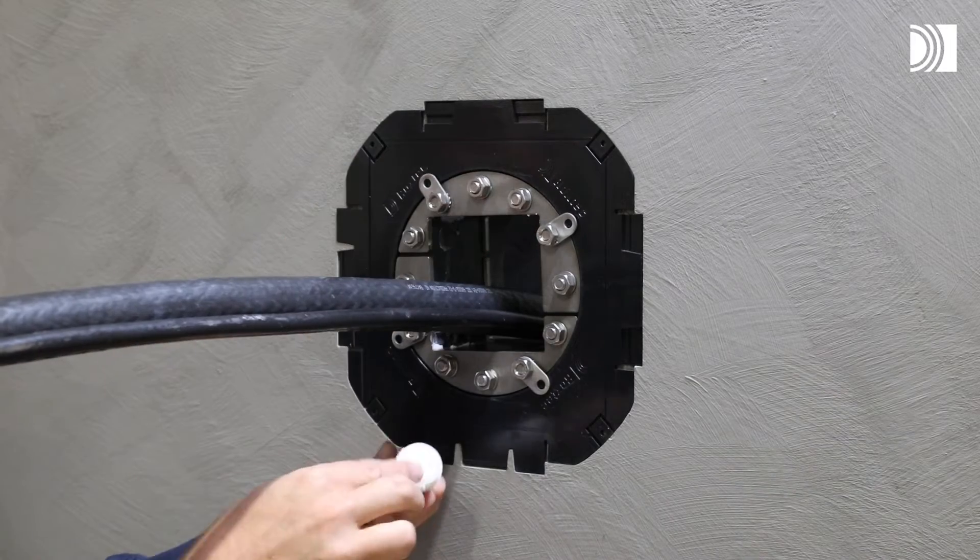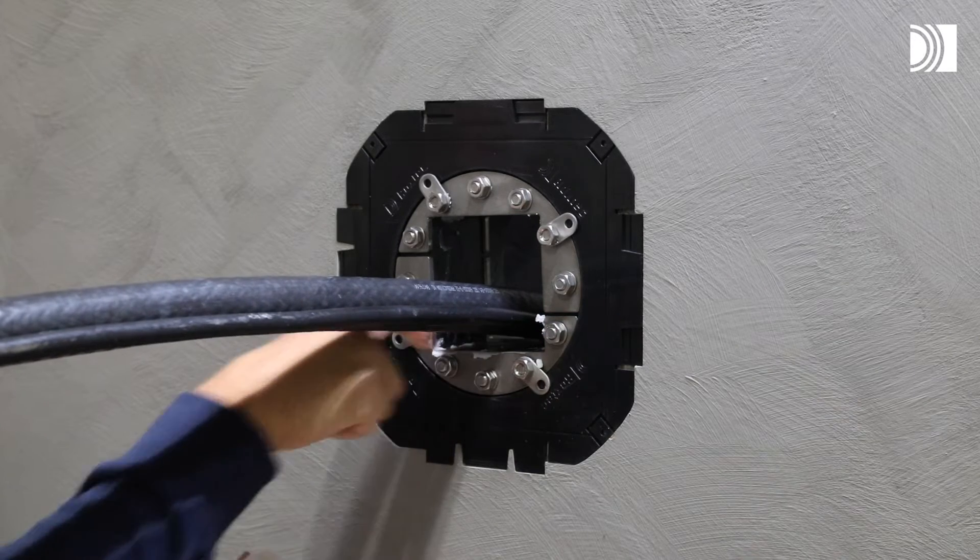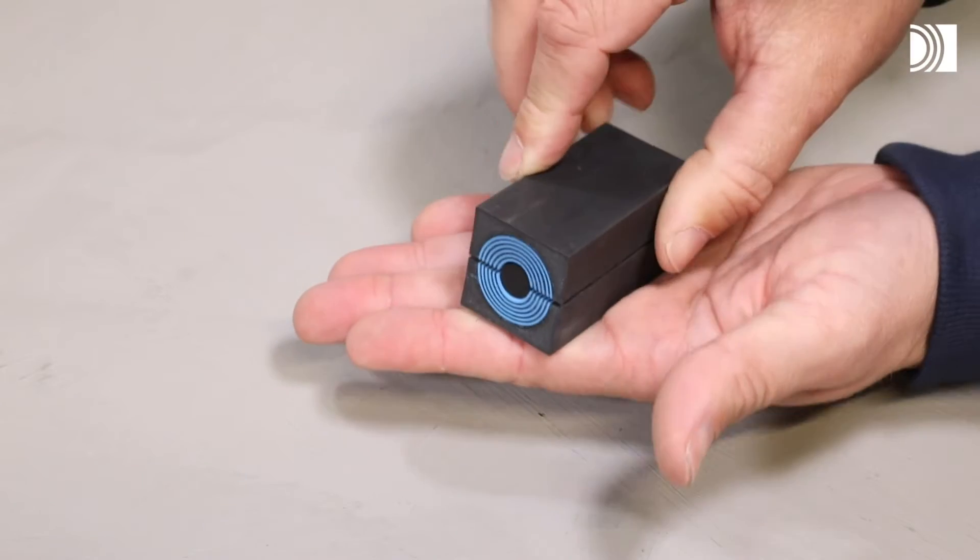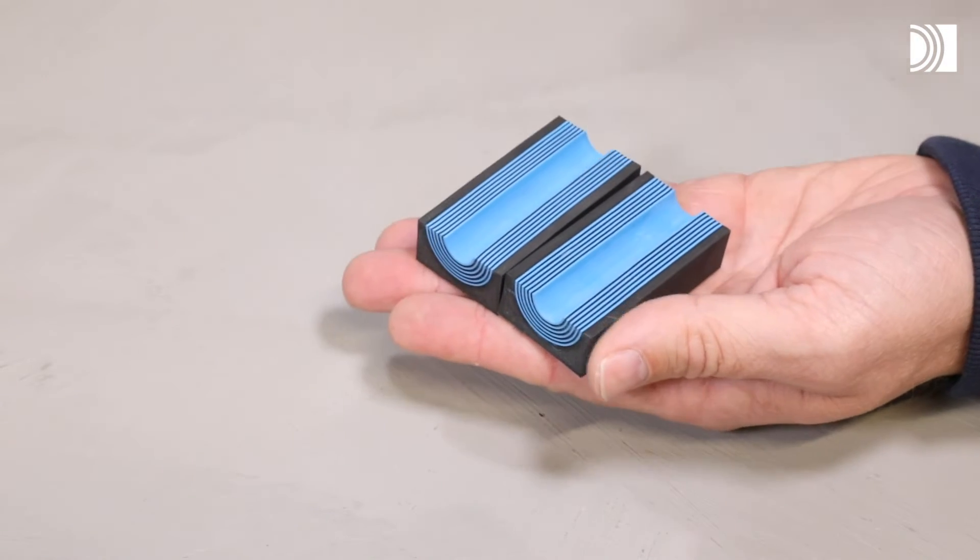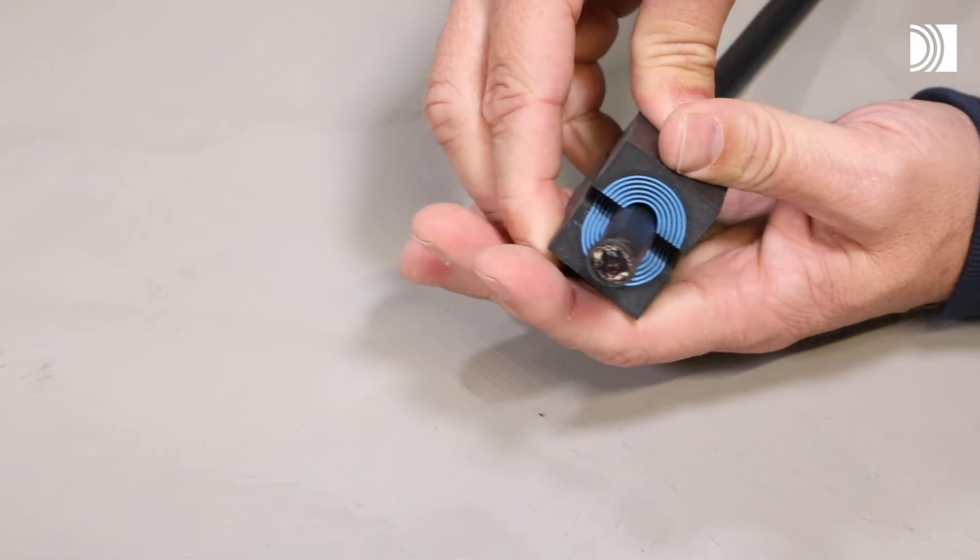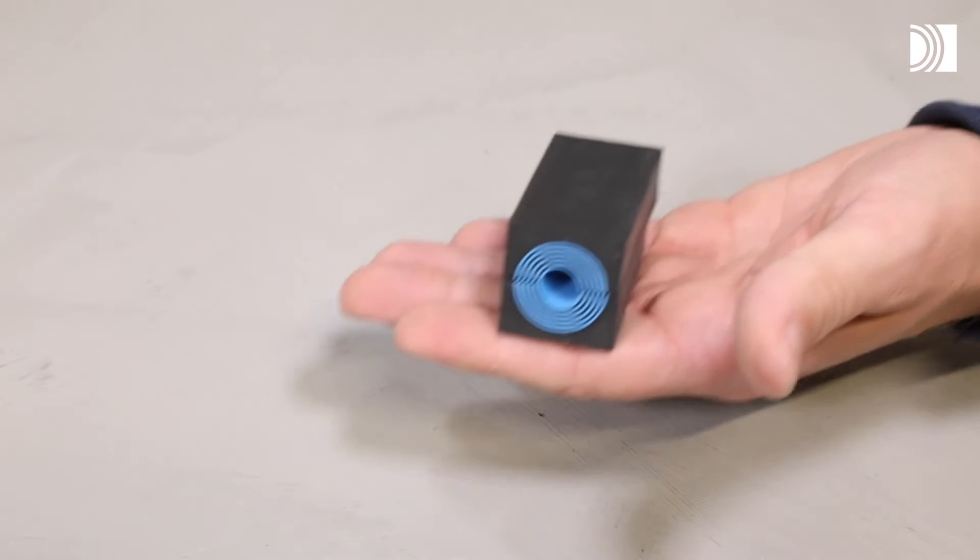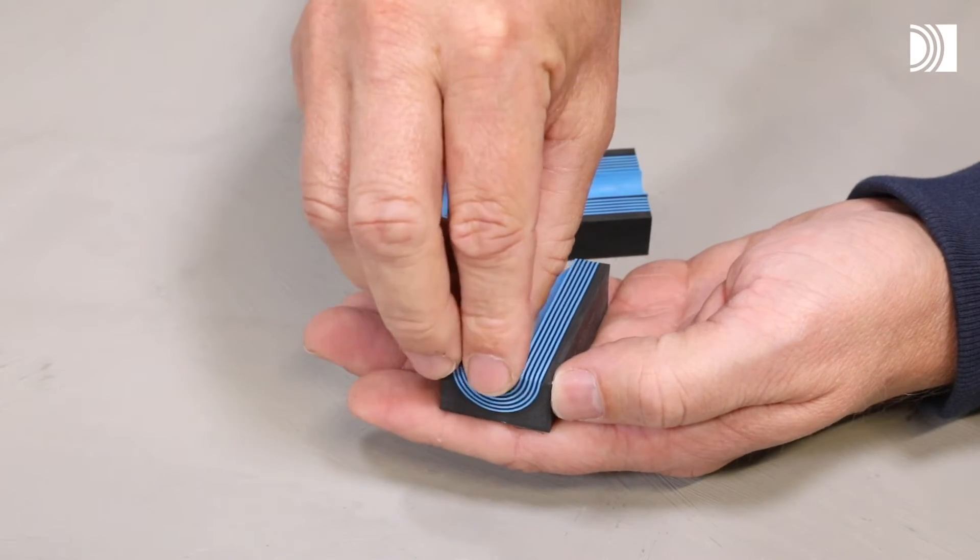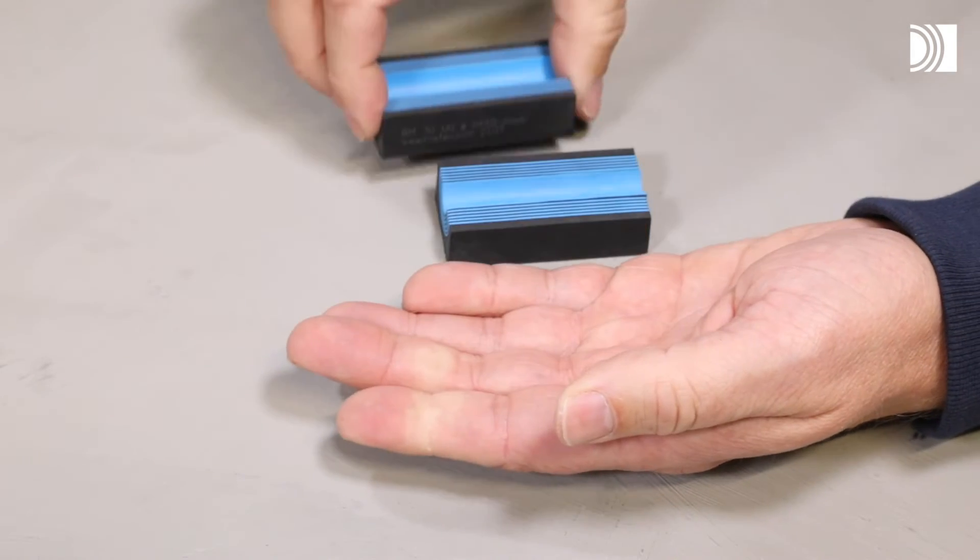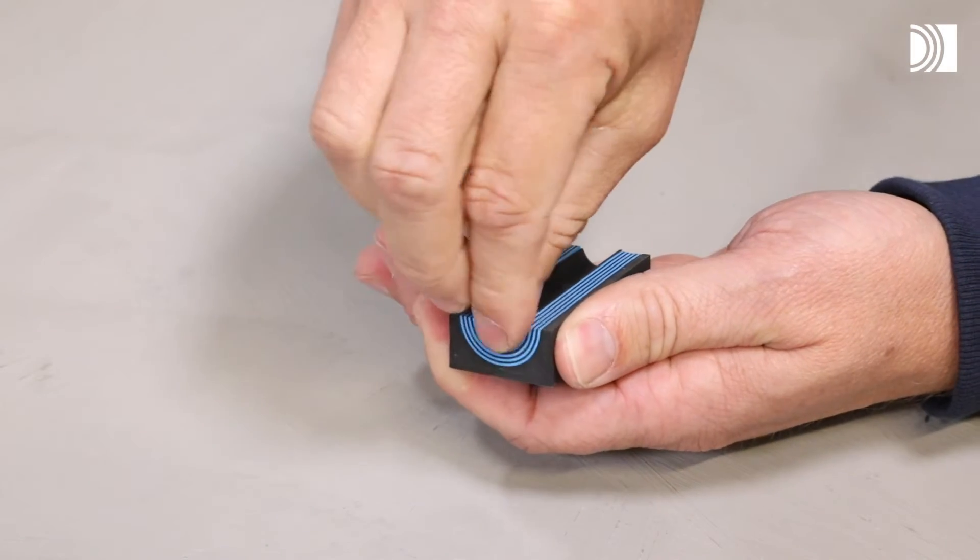Cables shall go straight through the frame. Adapt the modules. Achieve a 0.1 to 1 mm gap between the two module halves when held against the cable or pipe. Adapt the modules by peeling off layers. The number of layers may not differ by more than one between the corresponding module halves.